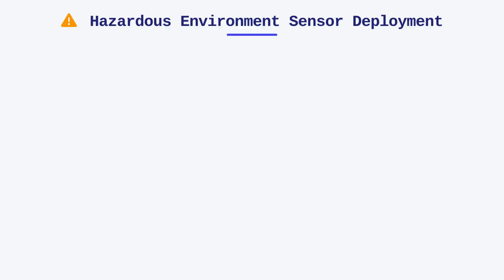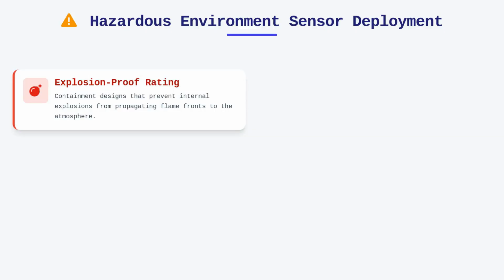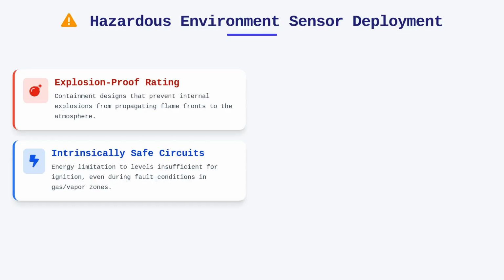Finally, you must navigate the constraints of hazardous environments where electrical energy could inadvertently trigger an ignition event. In these locations, thermal sensors must be rated as explosion-proof, meaning they are designed to contain an internal explosion without propagating a flame front to the surrounding atmosphere. For areas where gases or vapors are present, intrinsically safe circuits are required, limiting the electrical energy to levels insufficient to ignite the ambient hazard even under fault conditions.